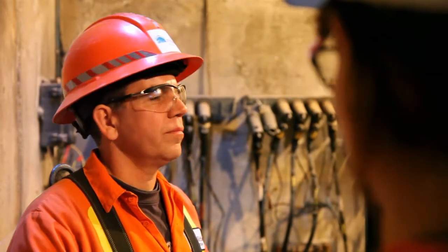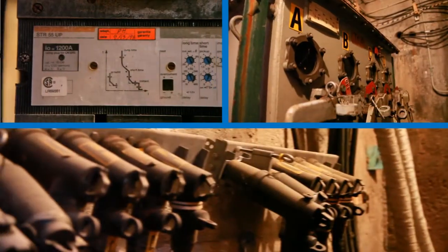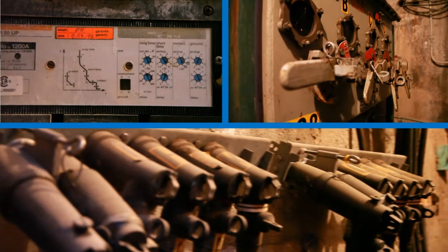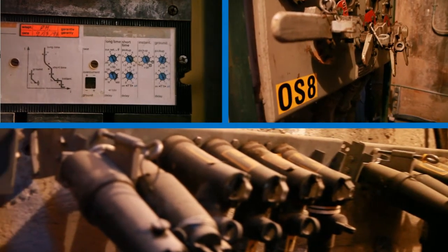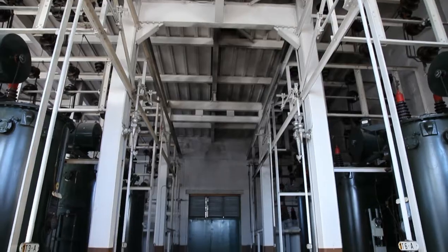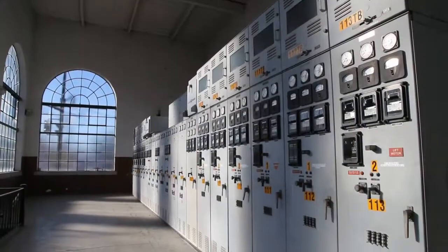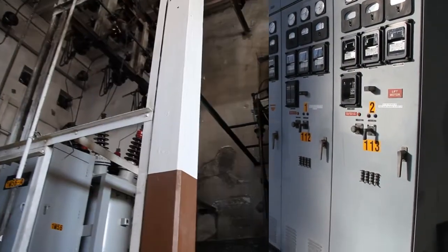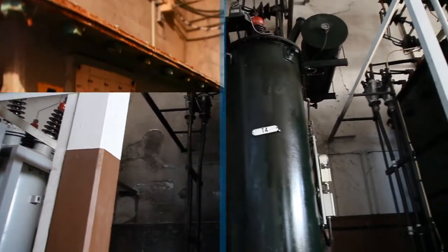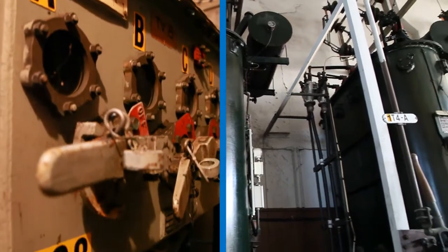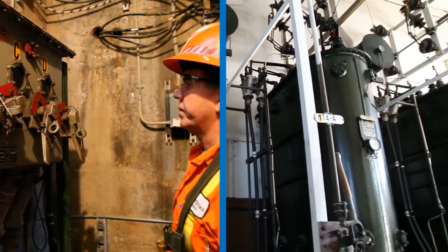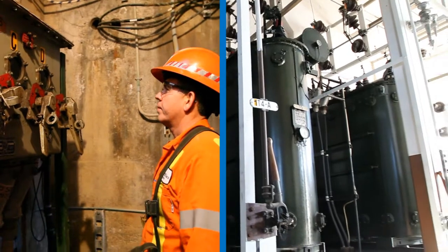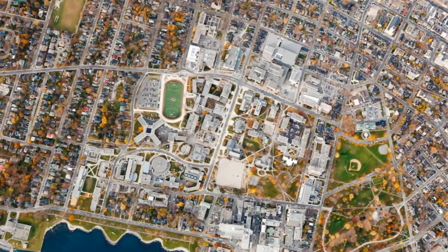The oil break switches that we're talking about are such that we cannot operate them when they're alive, or energized, with electricity flowing through them. So we actually need to go back upstream to switching points, a lot of them substations like the number 1 substation that we talked about, and de-energize a whole circuit before we can throw a switch here to isolate a smaller section. That results in a large number of outages and disruptions to customers of the City of Kingston.